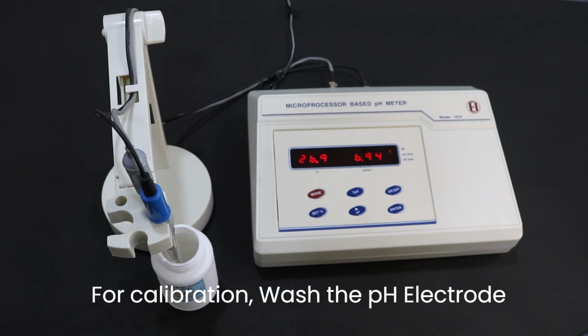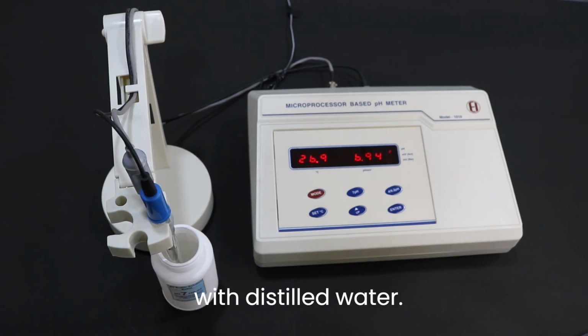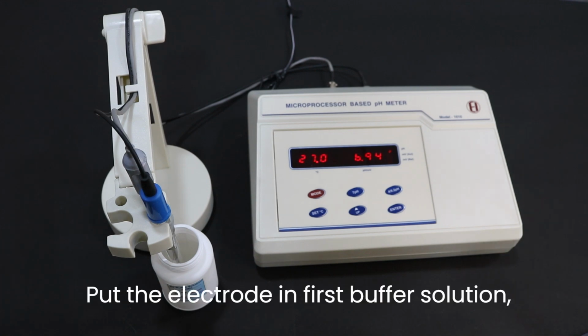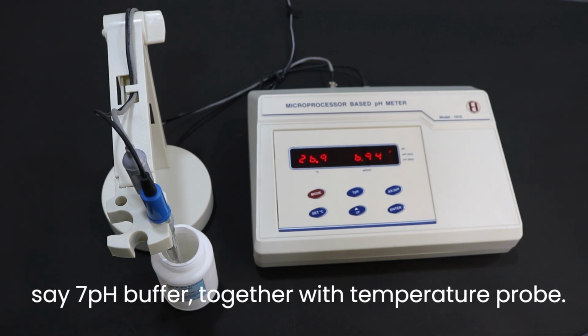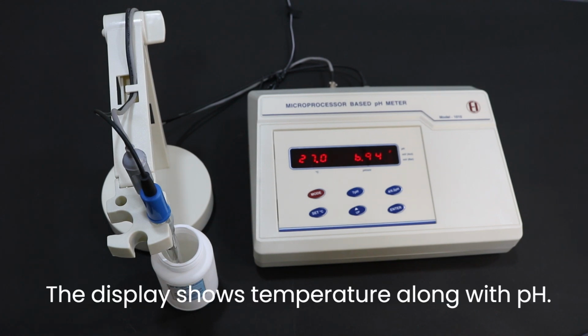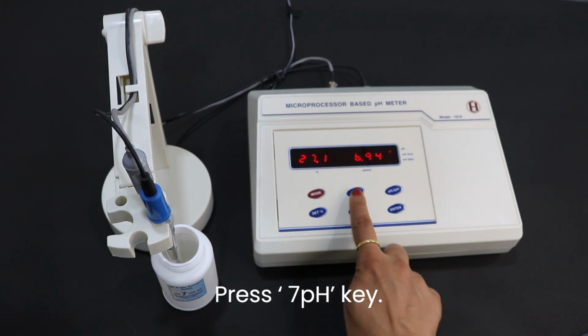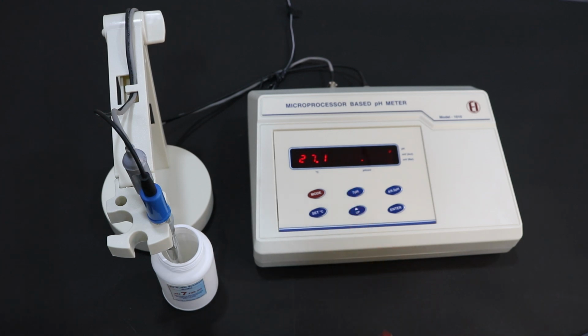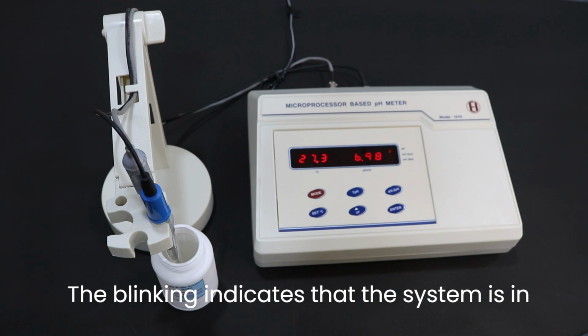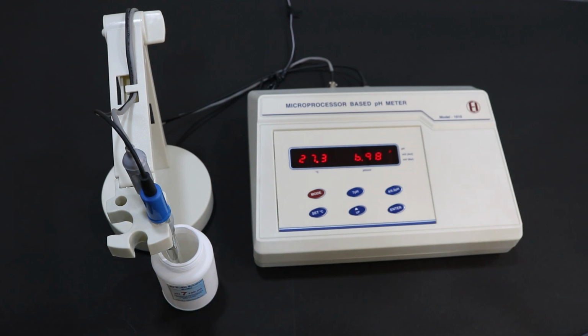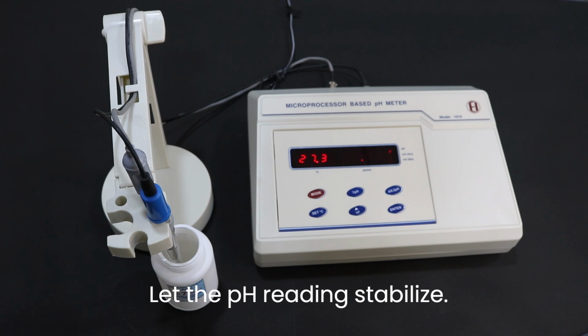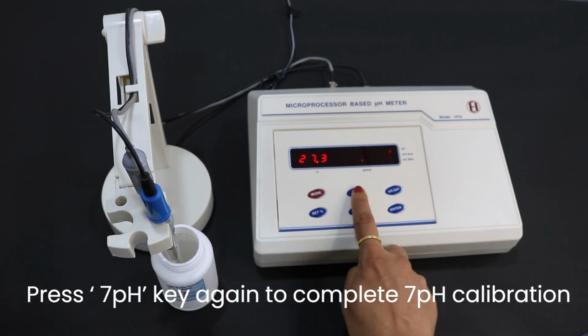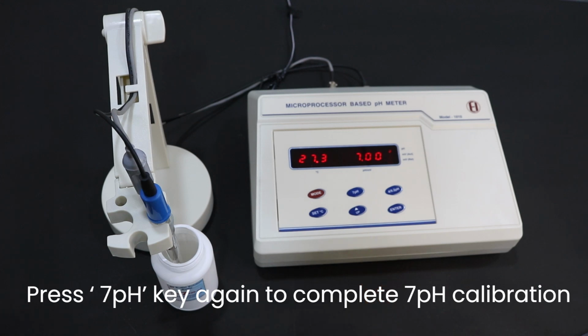For calibration, wash the pH electrode with distilled water. Put the electrode in the first buffer solution, say 7 pH buffer, together with the temperature probe. The display shows temperature along with pH. Press 7 pH key. The display starts blinking. The blinking indicates that the system is in calibration mode. Let the pH reading stabilize. Press 7 pH key again to complete 7 pH calibration.